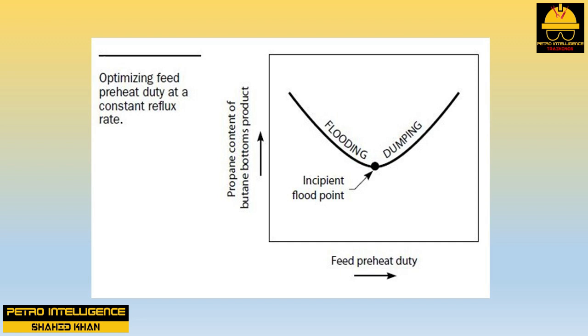This preheater duty corresponds to the incipient flood point. The optimum feed preheater duty maximizes fractionation at a fixed reflux rate. Varying the heat content of the feed is an additional independent variable that an operator can use to optimize fractionation efficiency. An additional benefit of feed preheat is that a lower temperature heat source can be used — if valuable 100 psig steam is required for the reboiler, then low-value 26 psig steam might be adequate for the feed preheat exchanger.